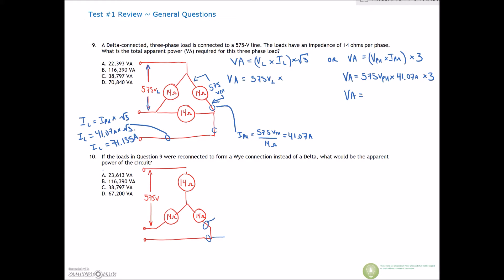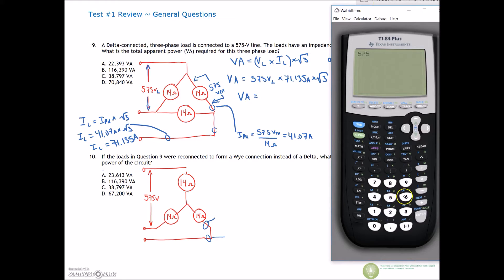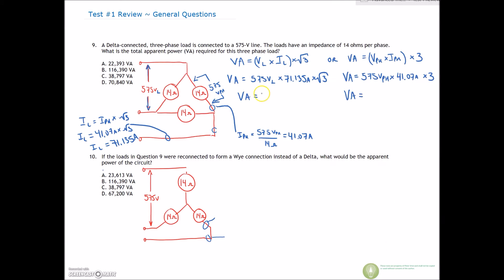That value is right here on our line, so we can drop that in — 71.135 times √3. So we've got 575 times 71.135 amps, multiplying that by the square root of 3, and that gives us 70,845.42. Very close to this answer value — just rounding would be the issue between the values.